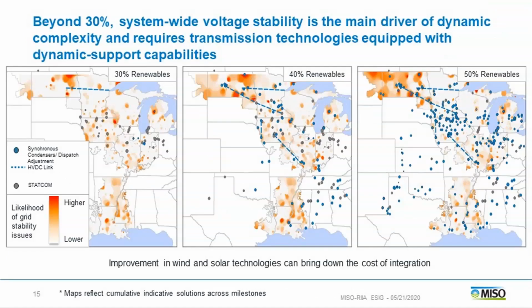As we dove into the reliability picture, we started seeing something a little different than what we normally see from our planning activities. Normally, much of the issues and needs in the system are focused around steady state voltage and primarily thermal problems. But beyond 30%, one of the main drivers of reliability needs focused around voltage stability, and this can be characterized as weak grid problems.